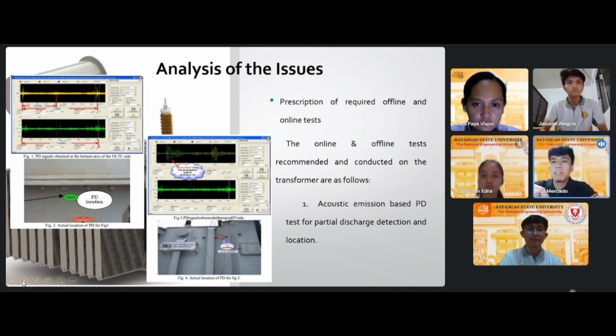Prescriptions of required offline and online tests. The online and offline tests recommended and conducted on the transformer are as follows. The first one is the acoustic emission based PD test for partial discharge detection and location.